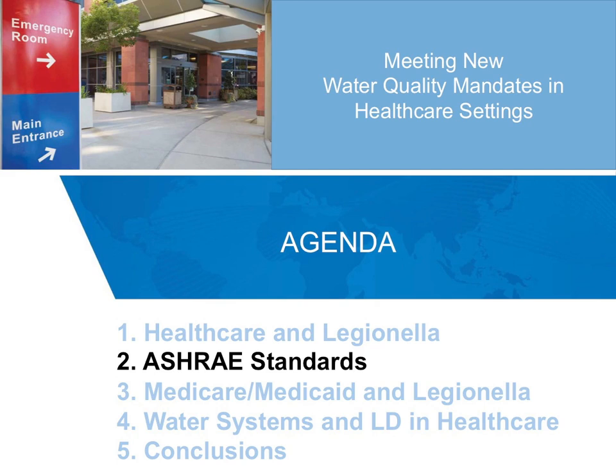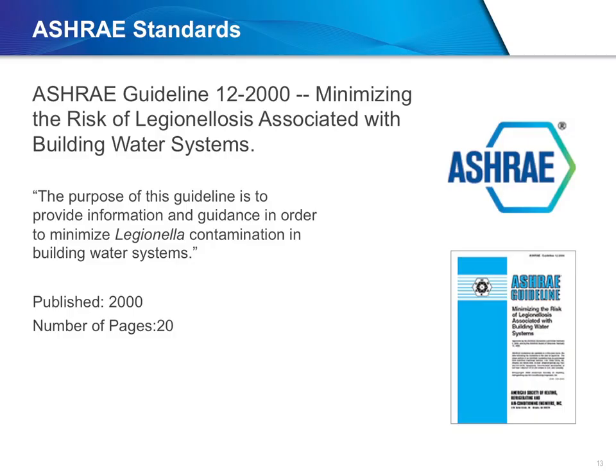Based on the facts and statistics about LD that we have just covered, it is not surprising that national standards have recently emerged to provide guidance to hospital personnel, but also to design professionals, in how to address this potential threat. We will look at the most notable ones developed by the American Society for Heating, Refrigeration, and Air Conditioning Engineers, otherwise known as ASHRAE. As a leading professional building engineering organization, ASHRAE has taken note of the connection between water-based mechanical and plumbing systems in buildings and Legionella bacteria growth.